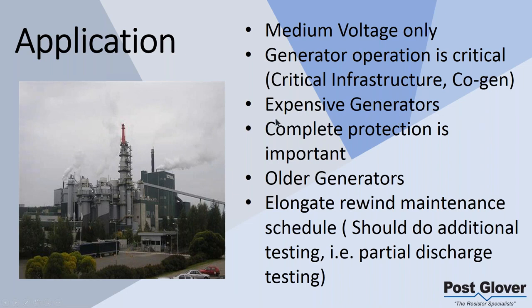Expensive generators. We're basically talking about insurance. We're increasing the amount of resistors we use for protection, specifically for faults internal to the generator. We're not protecting it against that at all if you have a solid ground system. We're protecting it against that a little bit, but not nearly enough, in my opinion, if you have a low resistance ground system. So the more expensive your generator, the more it's like buying insurance. You spend a little bit more money on the front end, but you protect yourself on the back end. Usually, you're more likely to use this the more expensive the generator is. You're not going to spend an extra $15,000 on something that is only $30,000. You understand what I'm saying?